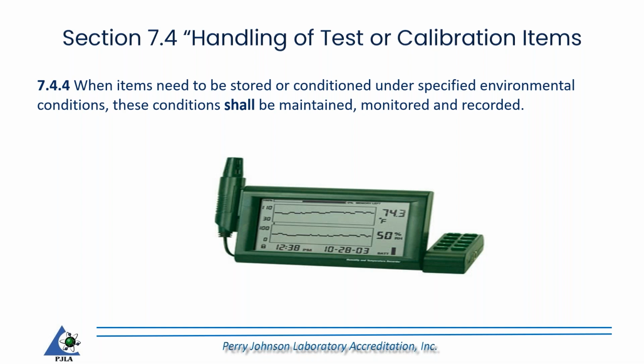If not done right away, and if they are stored, you need to create a record; it shall be maintained, monitored, and recorded. So that's an example of a data logger there, which I often see as objective evidence showing that this requirement is being met. Perhaps an alarm would go off if the predefined environmental criteria were to creep outside those predefined limits of acceptance.